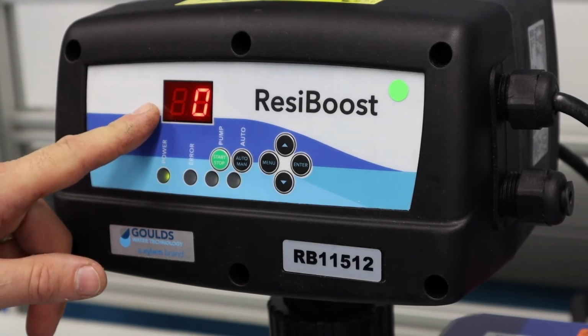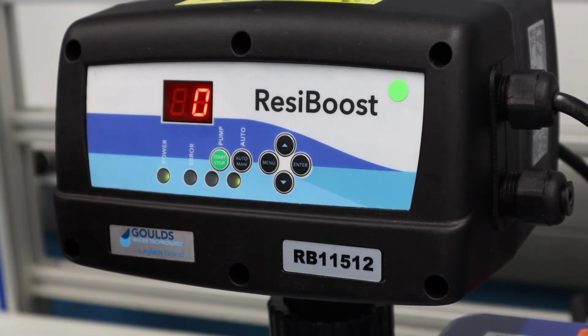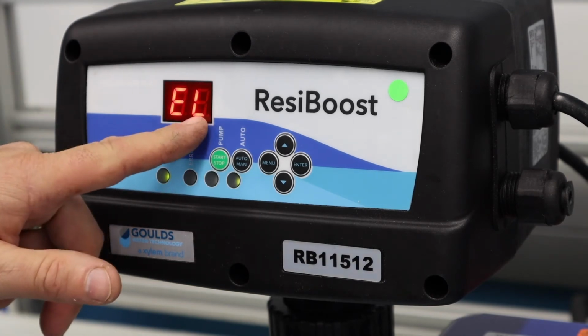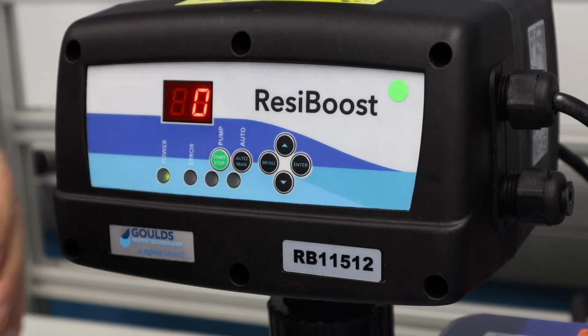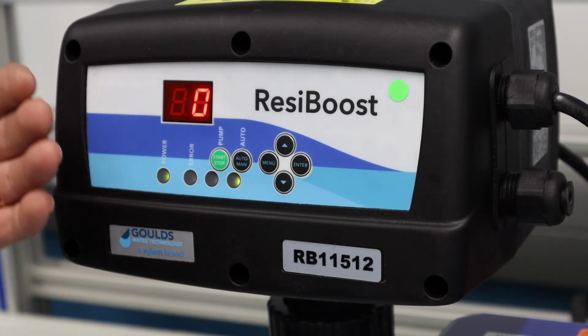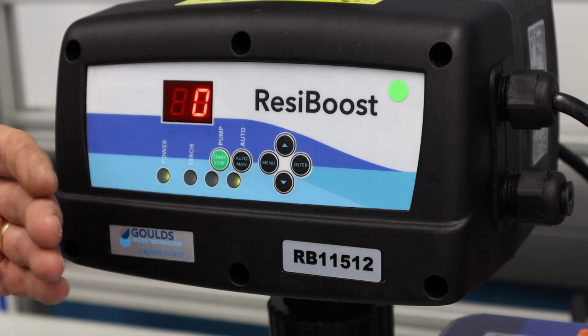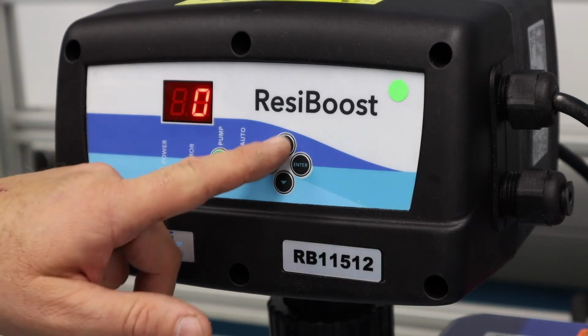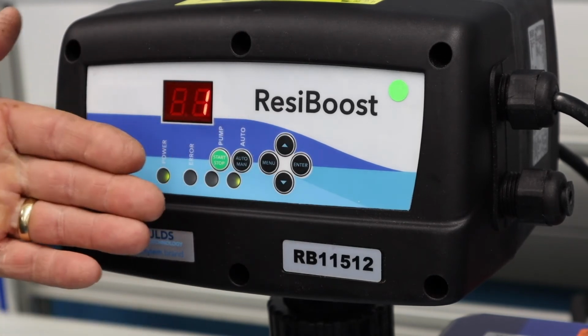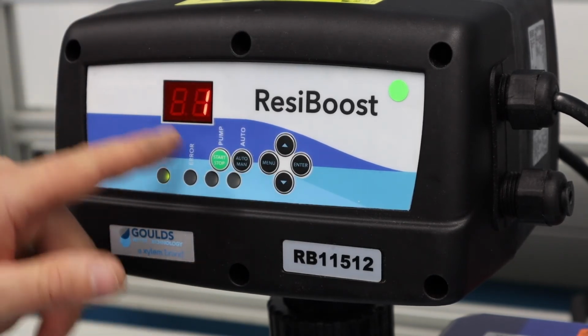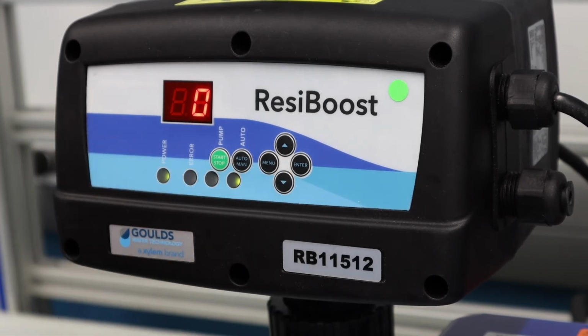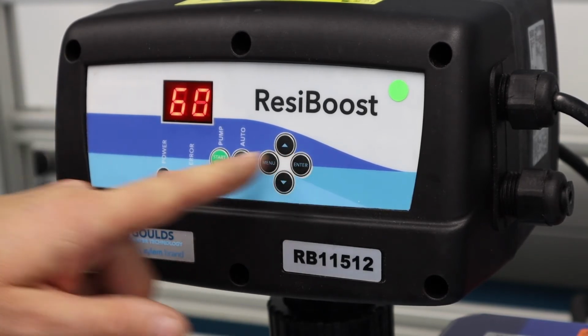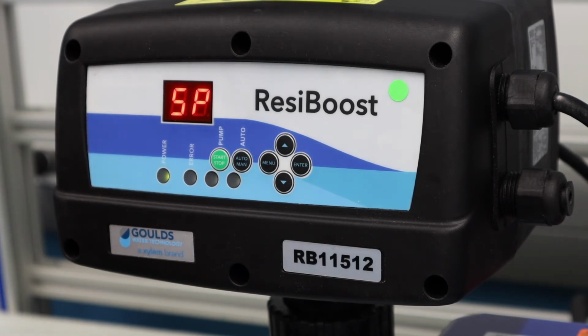low water. And we can see the default is 0. That means it's disabled. I don't have another switch, whether it be a pressure switch or float switch, going into this system to protect it for low water. So I want to leave that at 0. If I did have a low water switch on the suction side, maybe it's pumping from a tank or something, then I would change that to 1. That would be enabled. But if you don't have any low water switch, make sure it is 0, which is the default.